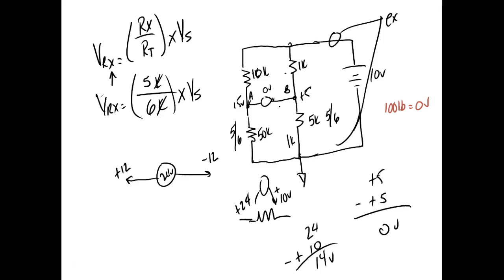Same ratio. Now in the load cell, they're going to be the same because the strain gauges have the same unloaded resistance—except this one right here, the active gauge, is varying with force, while this guy here is varying with temperature. Does that make sense? So what happens is they compensate for each other.